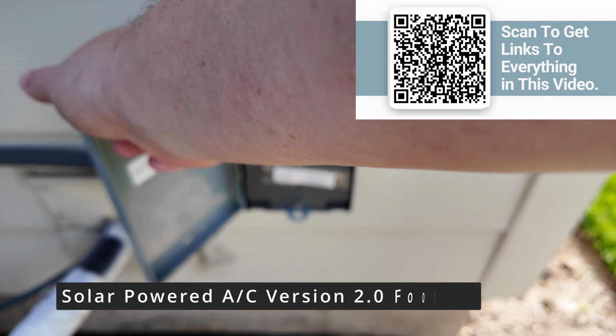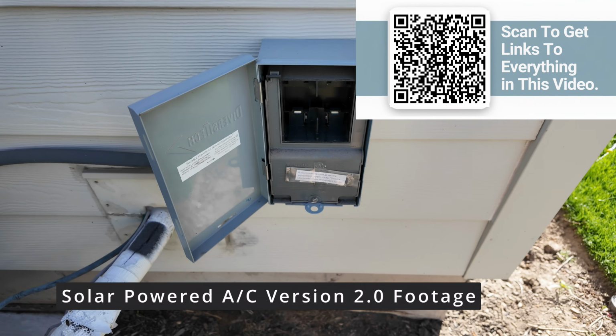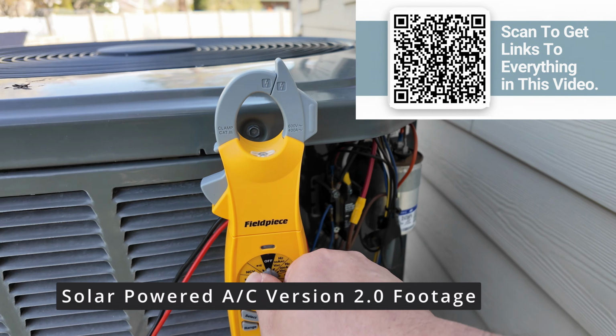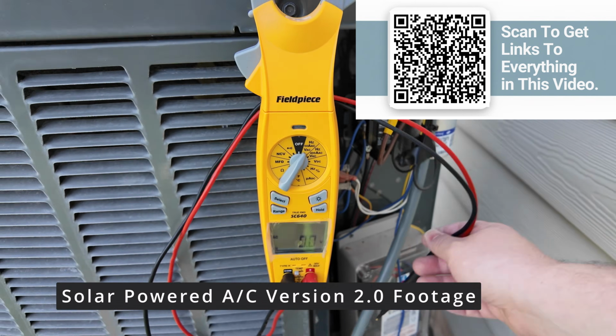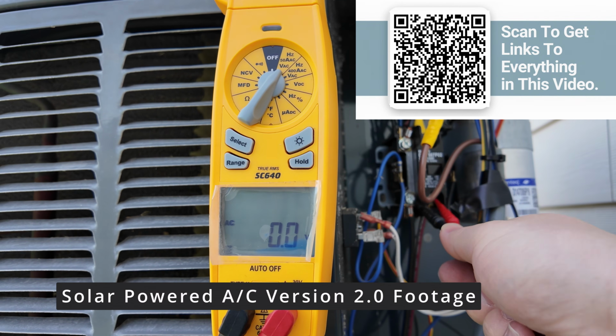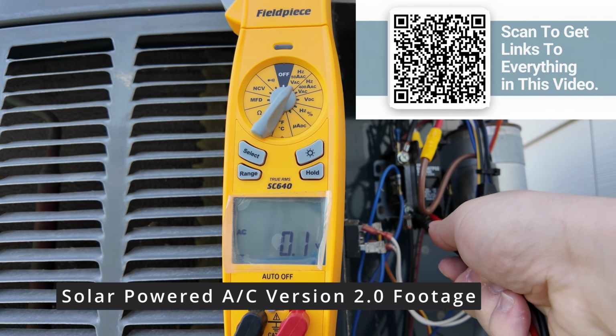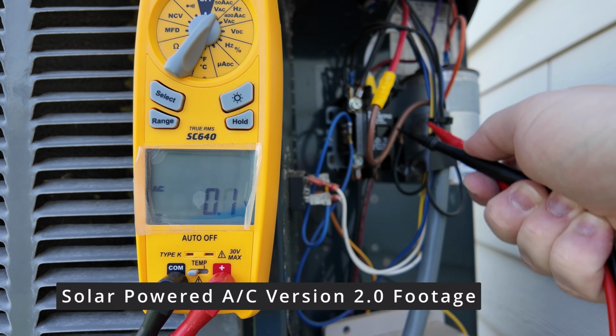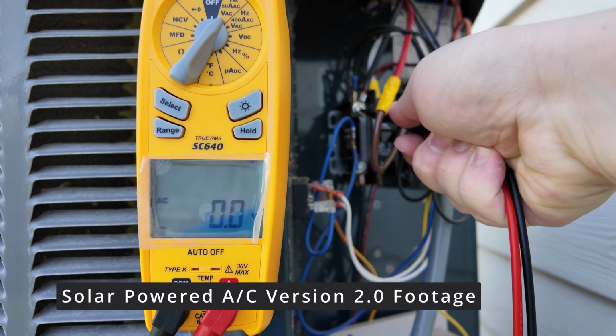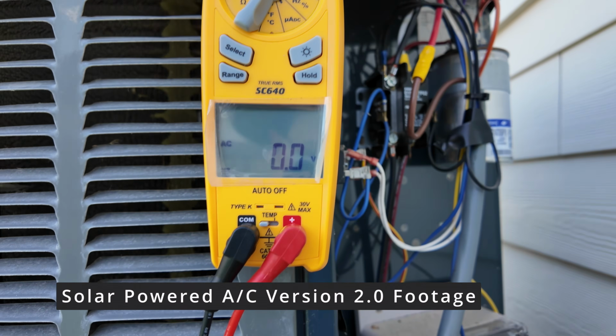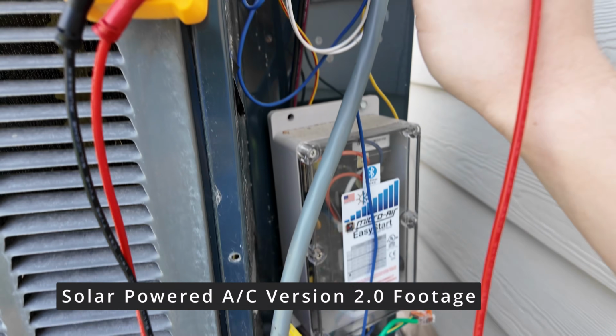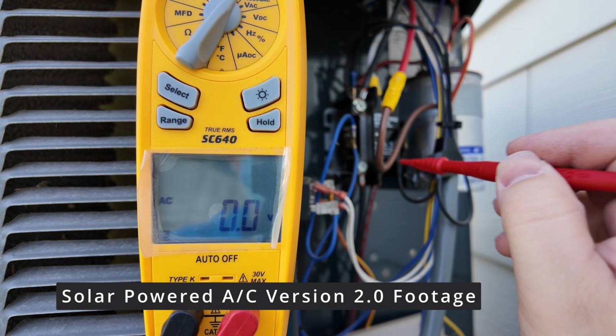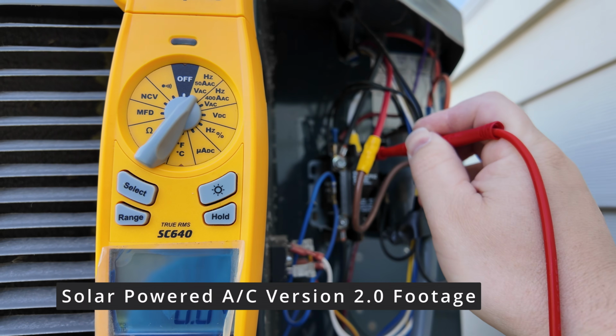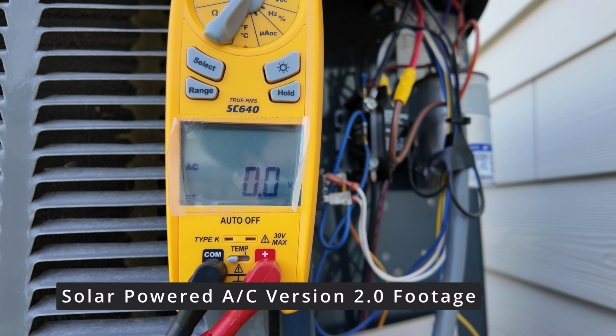All right, first and most important, safety first. We're going to come here to this service disconnect, pull that out, and check with this voltmeter to make sure there's no power coming into this unit. No voltage there. Check the top of the contactor as well, just for good measure—no voltage there. Then I'm going to ground one of my probes and test each leg to ground. Nothing, nothing, nothing, nothing. So we're good to go there.